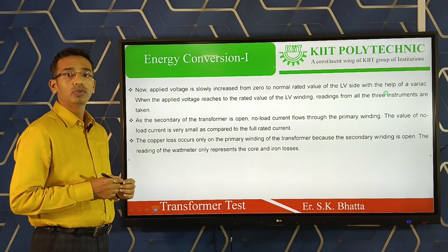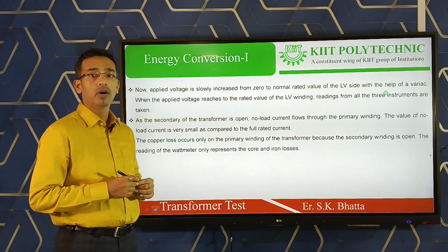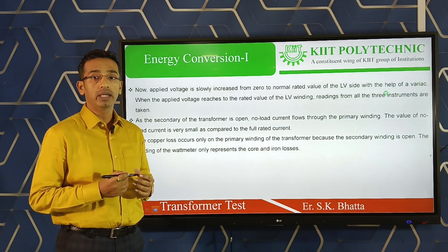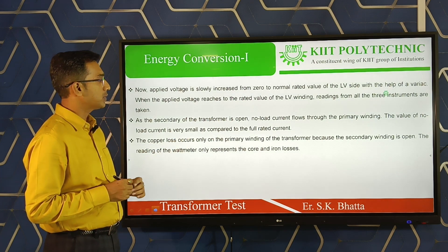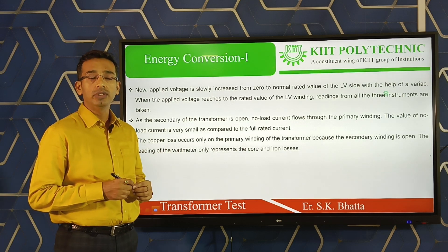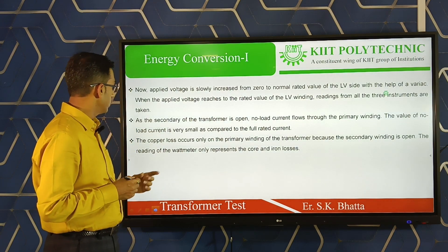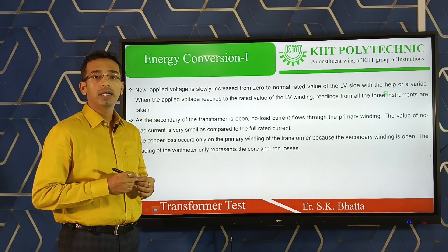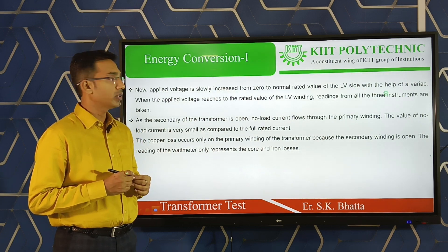Since the secondary side is open, no-load current flows through the primary winding. The no-load current is very small — about 4 to 6 percent of the full-load current. The copper loss occurs only in the primary side, and since the current is small, the copper loss is negligible. Therefore, in the open circuit test we measure the core loss or iron loss of the transformer.